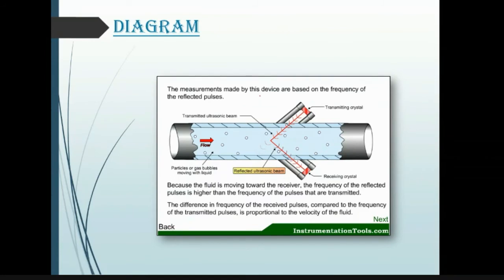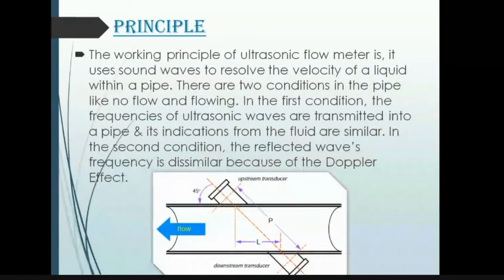Basically, the working principle of an ultrasonic flow meter is that it uses sound waves to resolve the velocity of a liquid within the pipe. There are two conditions in the pipe, no flow and flowing. In the first condition, the frequencies of the ultrasonic waves transmitted into the pipe and reflected from the fluid are similar. In the second condition, the reflected wave frequency is dissimilar because of the Doppler effect. The Doppler effect is another topic which, if we go into detail, would be really confusing.